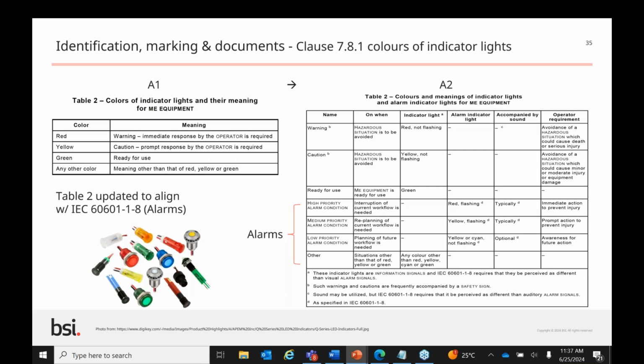There's also lots more info to read and a footnote section at the bottom of the table, which points a lot to the 1-8 standard. It's highly recommended that all manufacturers obtain a copy of the current version of IEC 60601-1-8 to fully understand the alarm requirements. I know, another standard, that's always an issue. Many manufacturers actually should apply it even though they think they only have notifications. If you're using risk management as a mitigation for notification, then you actually have an alarm. Next slide.